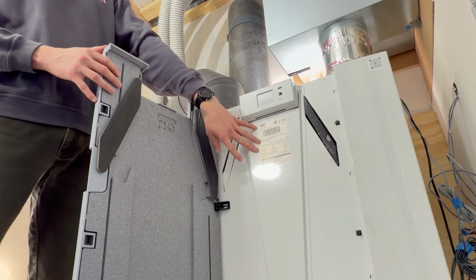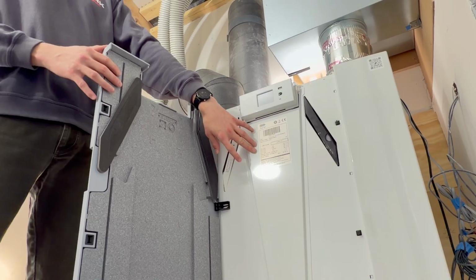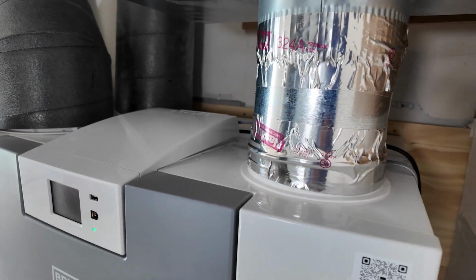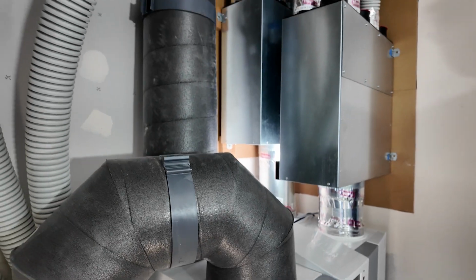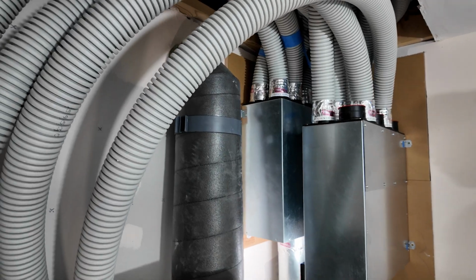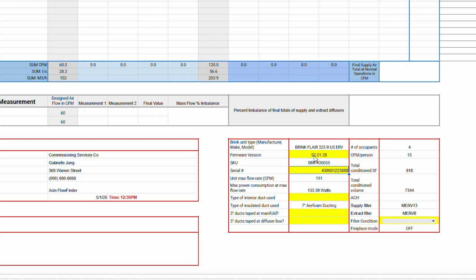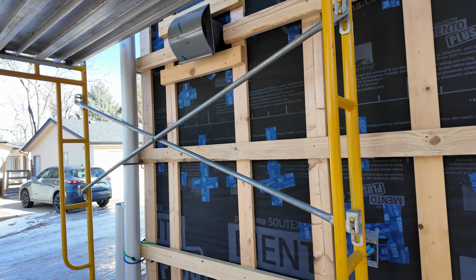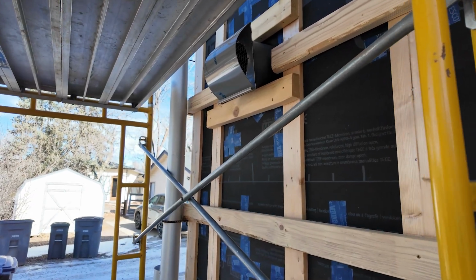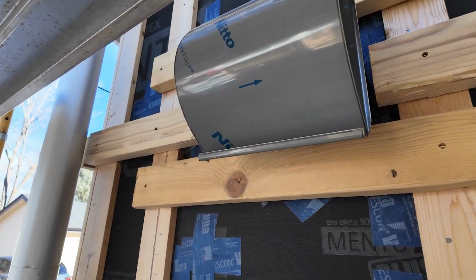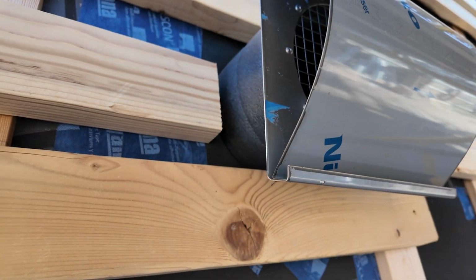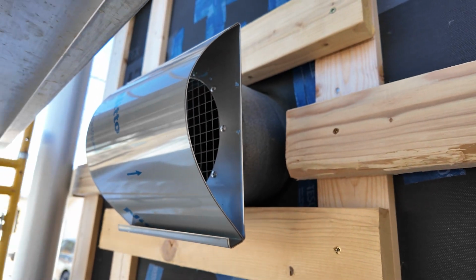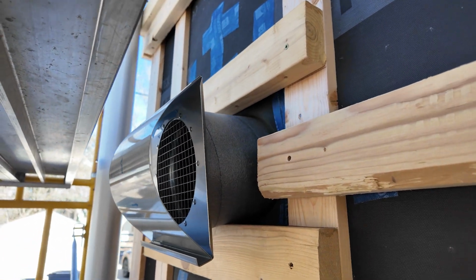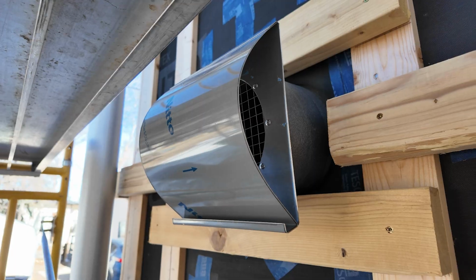The commissioning agent should take a photo of the type plate, the installation setup, including details like manifold placement and the exterior grills. The serial number should be recorded on the sheet. Outside, make sure the intake is providing the freshest air possible, is located above the snow line, and that there are no restrictions such as leaves or debris on both intake and exhaust grills.